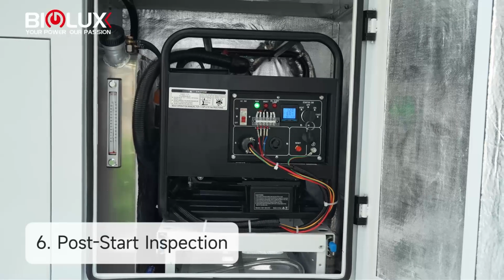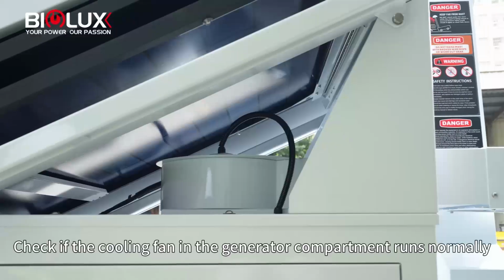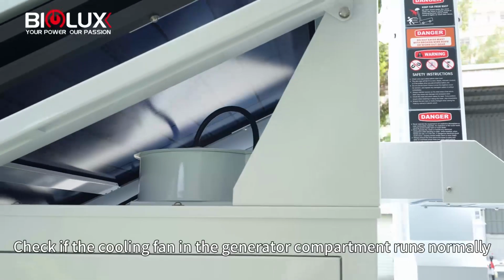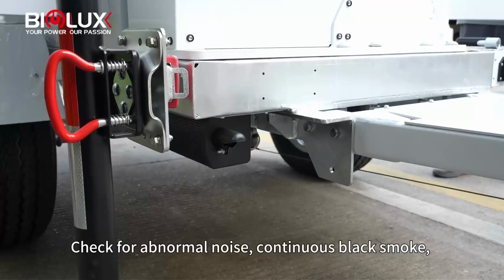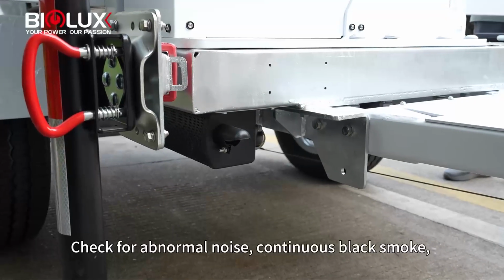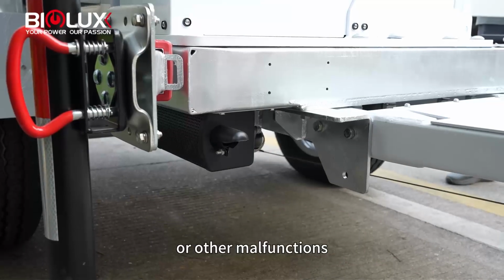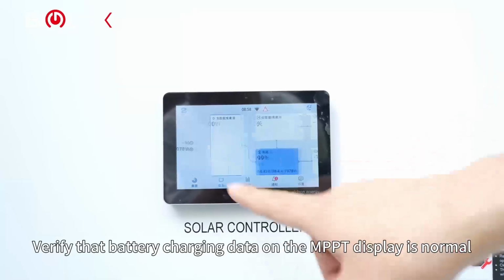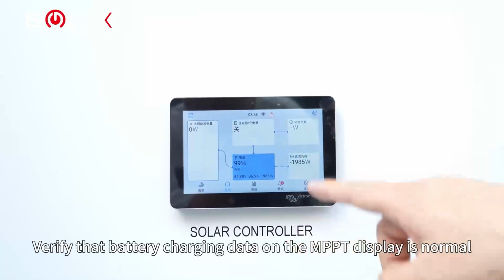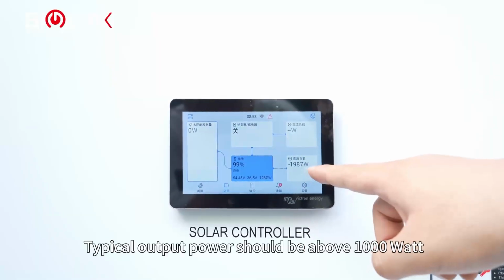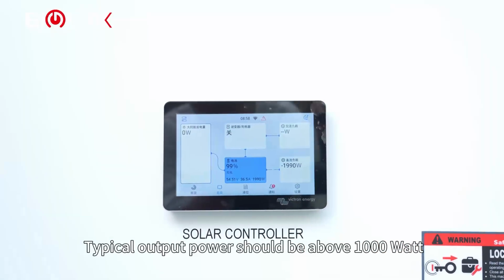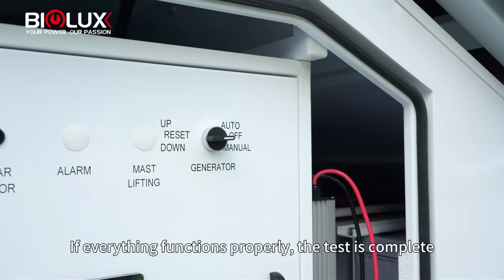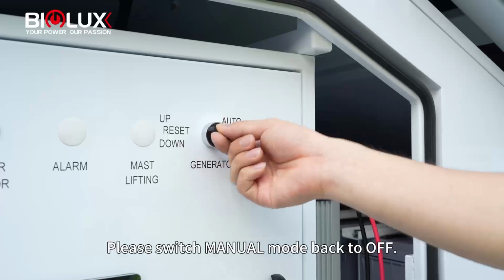6. Post-start inspection. Check if the cooling fan in the generator compartment runs normally. Check for abnormal noise, continuous black smoke, or other malfunctions. Verify that battery charging data on the MPPT display is normal. Typical output power should be above 1000 watt. If everything functions properly, the test is complete. Please switch manual mode back to off.